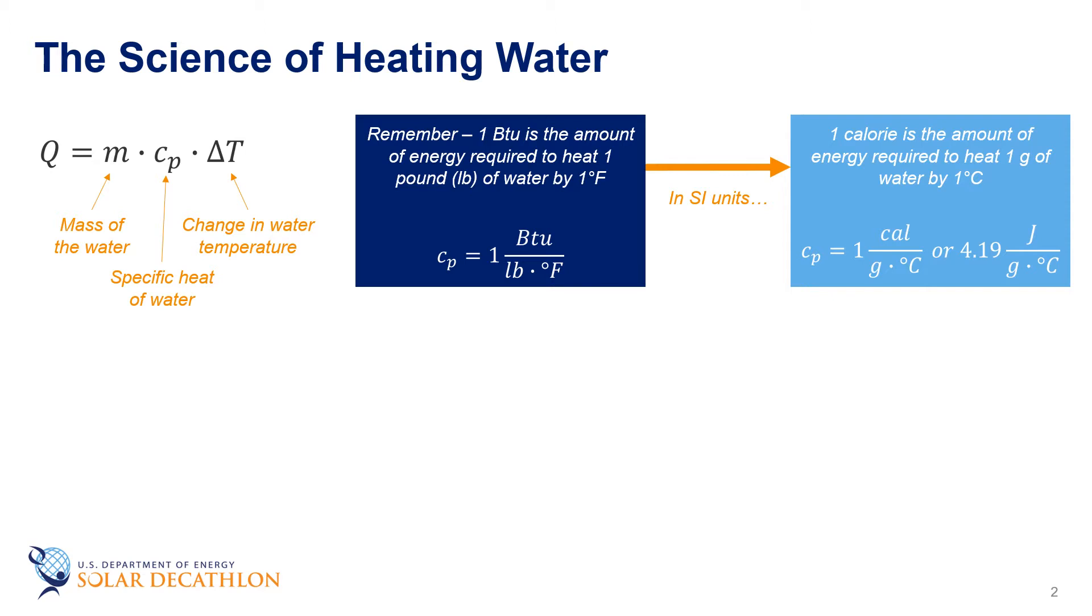We typically measure water as volume and not mass, so density times volume is mass and we can rewrite the equation as Q = ρ · V · cp · ΔT. If the density, specific heat, and temperature difference are constant, we can also write this as a rate or Q̇ = V̇ · ρ · cp · ΔT. The density of water is 8.32 pounds per gallon.